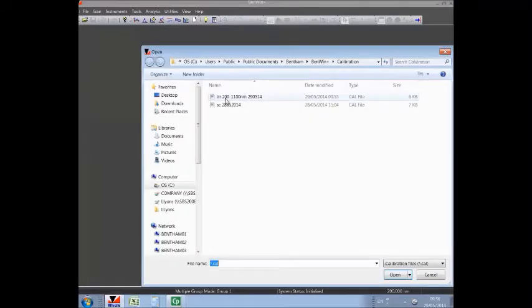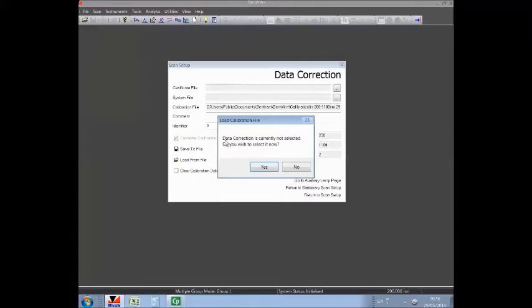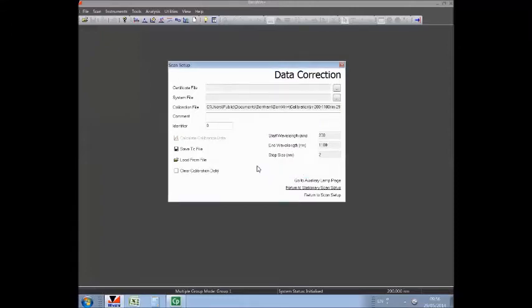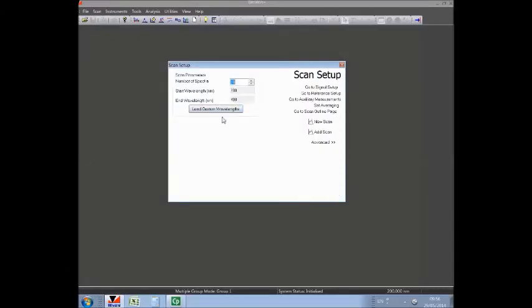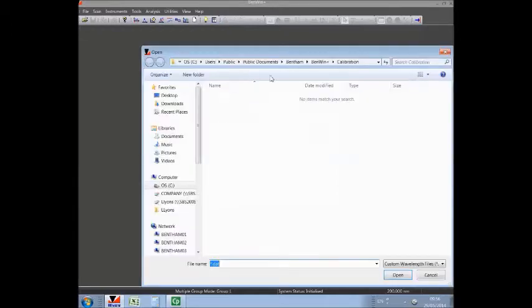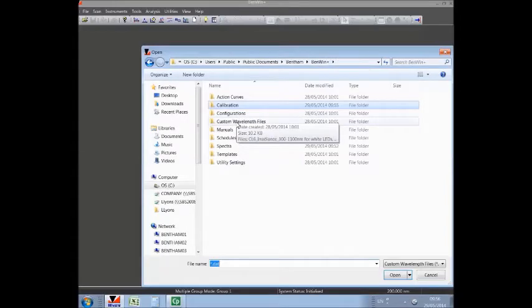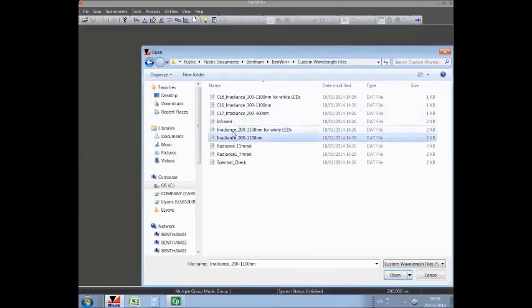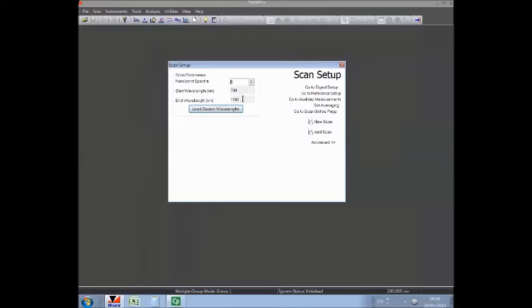We need to go to Scan Data Correction to load that calibration file, this new calibration file. Data correction is not selected. Do you wish to select it now? Yes. And actually, one final step is to modify the custom wavelength file, because now we are measuring 200 to 1100 nanometers. So in the custom wavelength files folder, we will find two Irradiance 200 to 1100 nanometer custom wavelength files, one to correspond with the CL6 Irradiance that we used, and one to correspond with the CL6 for white LEDs. We used the CL6 300 to 1100, so we should use this one. And we can now proceed to measure sources over the full range, selecting one or two spectra in the measurements.